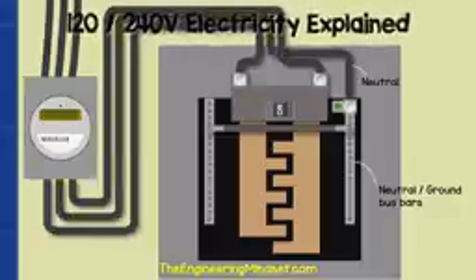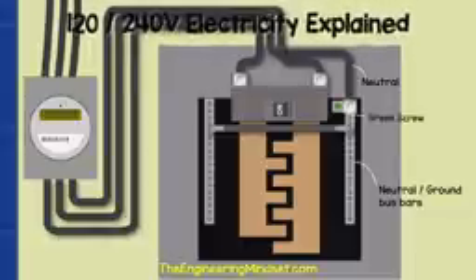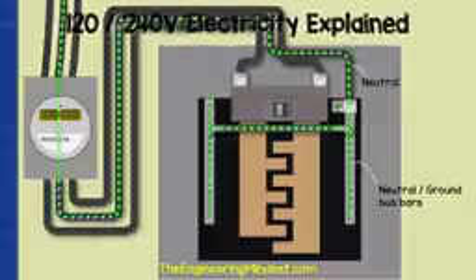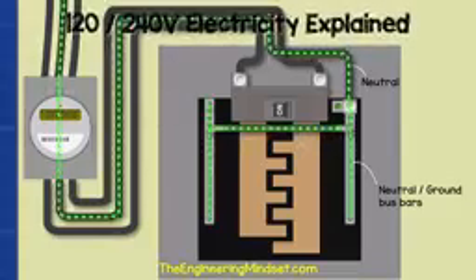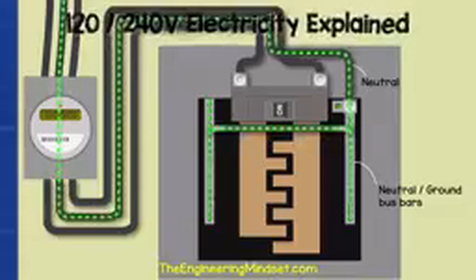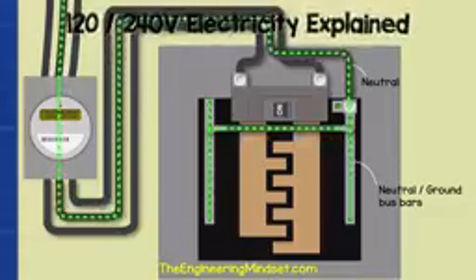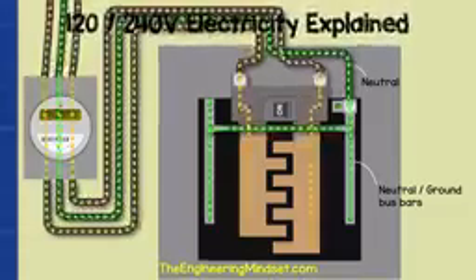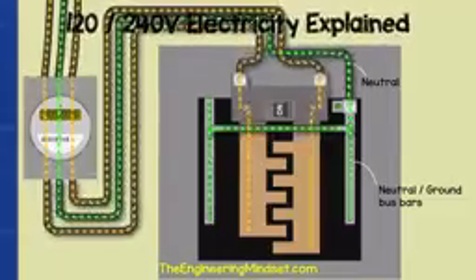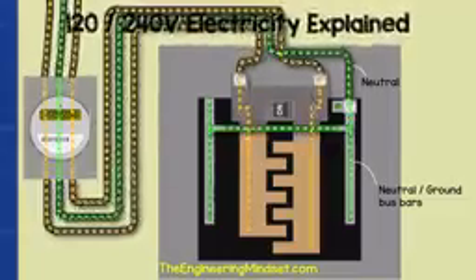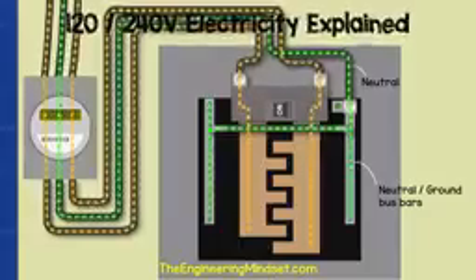From the electricity meter, we will have the neutral wire connected to the lug on the top of the neutral ground bar. Notice the green screw. This is bonding the neutral bar to the metal casing of the service panel. The purpose of the neutral bar is to return the used electricity back to the transformer. It does actually get a little bit more advanced than that, but we're going to look at that in a more advanced complex video. This is just covering the basics. So the 2 hot wires will provide the electricity, and once it is used, it will return to the transformer via the neutral bar.